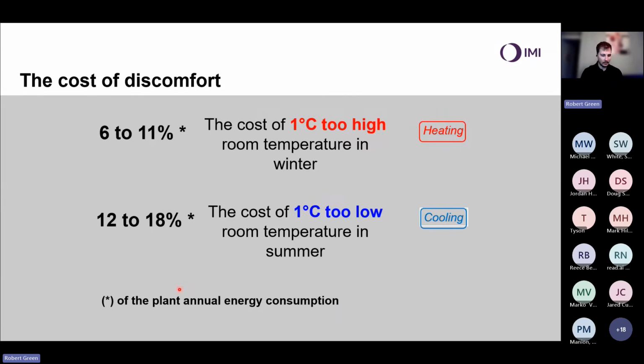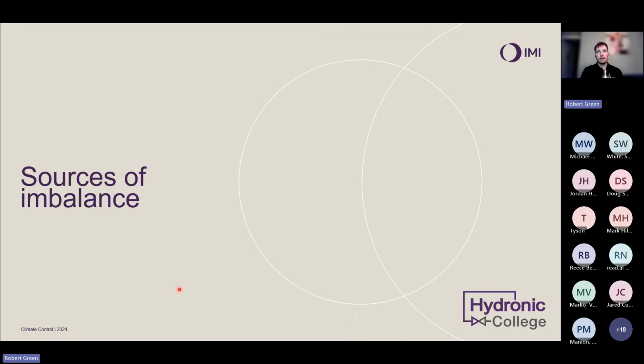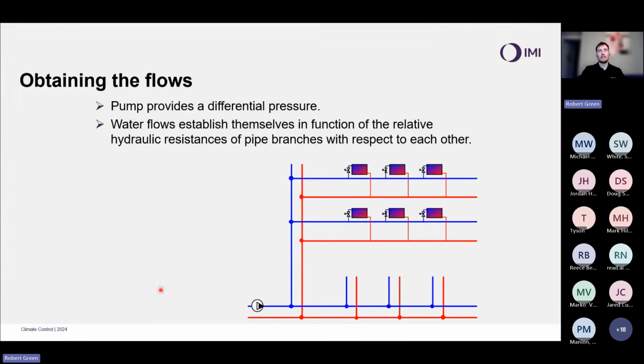What I want to look at is actually some of these sources of imbalance here as well. Now, if we look at sources of imbalance, I'm going to start now talking about coming away from flow and actually talking about differential pressure. And if we look at this system here, so we have a cooling system here serving a number of floors, a number of risers, and a number of emitters. These could be, say, fan coil units on each floor.